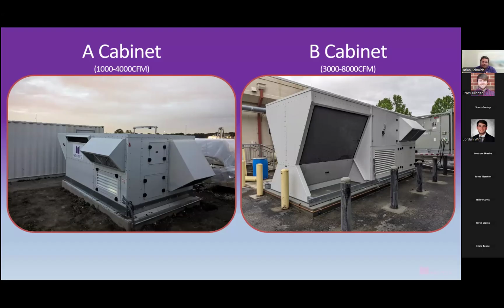Again, a real life example here on the A cabinet: you can see the outside air hood is that thing on the far right. That's the outside air tunnel on the other side of the unit. What you're seeing on this side of the unit is the regeneration tunnel, where outside air comes in through that smaller hood that's closest to us, passes through the hot gas reheat coil, heating up, and then goes across the desorber pad where that Mojave logo is. The desorber pad is behind that, and it flows out of the top of the unit itself.